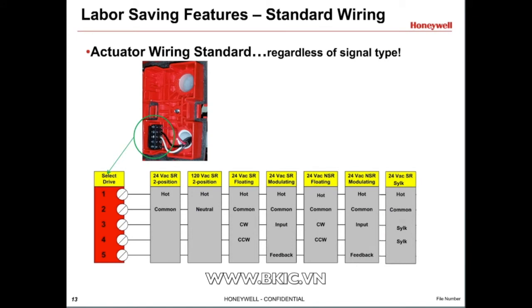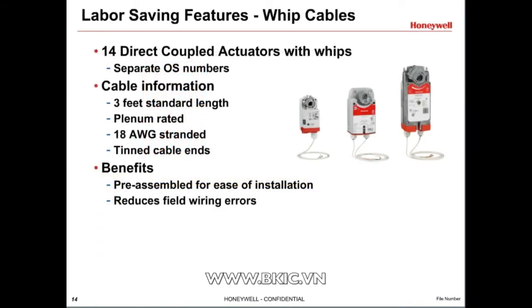To make the wiring simple and easy to learn, all Honeywell DCAs follow a wiring standard. Terminal pin 1 is always hot, and pin 2 is the common or neutral. Pins 3 and 4 are the control signal, such as floating, modulating, or Silk Bus. Pin 5 is used for feedback on modulating models. To simplify the wiring even more, you can order Honeywell DCAs with a 3-foot cable or whip. The whip is pre-wired to the actuators, so you only have to wire it to the controller. This reduces wiring time and the risk of miswiring.